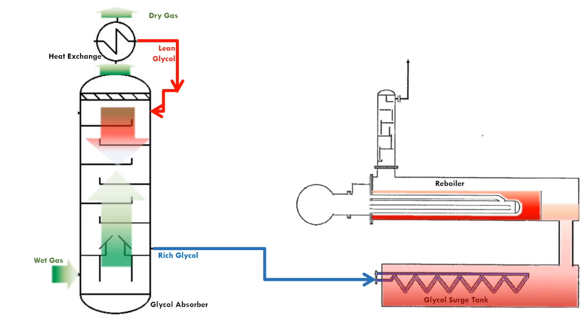The rich glycol flows through the coils in the glycol surge tank. The purpose is to preheat the rich glycol. This will increase the efficiency of the regeneration process as the process needs to increase the rich glycol temperature to remove the water.